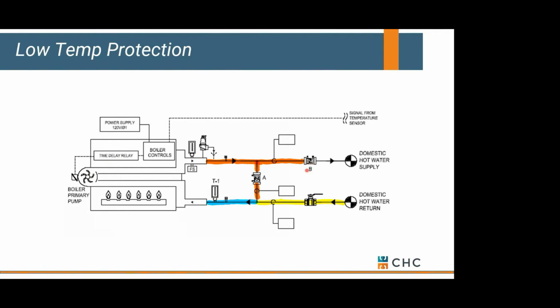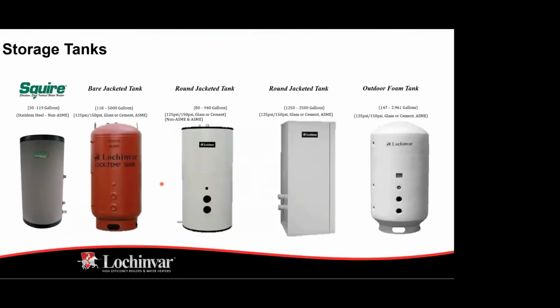We create some resistance, and we force some of that hot water right back into our return through this little bypass. We can trim it out with circuit setter A, but ultimately the goal is to throttle circuit setter B until we get enough return water that our temperatures start to rise. Once they get above 130, you can lock in or dial in your circuit setters and walk away. Because every time the water heater starts, we're going to get 90 to 100 degrees coming out of our storage tank. So this is how you would protect a non-condensing water heater. If you don't do that, you've got about 6 months and counting before you might have to walk in there and replace it. It doesn't like to work in a condensing mode.